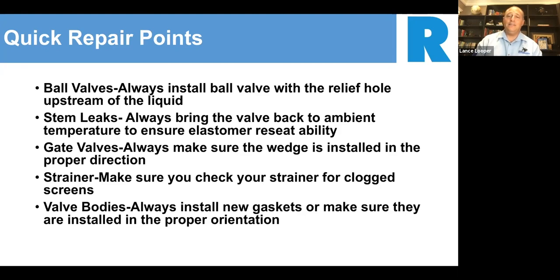I can't tell you how many times I've seen those installed the wrong way, and it will ruin the wedge, and that valve will never, ever operate right again. Just something to keep an eye on. We have full instructions on how to do that. Feel free to reach out to us if you need any help.